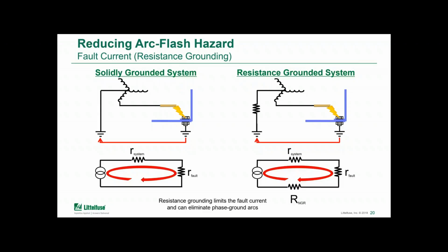So just to clarify what we mean when we talk about the arc flash on the first ground fault and how resistance grounding can mitigate that, here's an example of a ground fault both on a solidly grounded system and a resistance grounded system on the right side. You can see that the amount of current is going to be limited by two impedances. One is the impedance of the system, and one is of the fault. The resistance grounded system on the right side has an additional impedance, of course, which is the neutral grounding resistor itself. If the resistor is sized appropriately, and in most low voltage applications that would typically mean 10 amps or less, we can eliminate the risk of arc flash on the first ground fault because of that additional impedance in the loop.